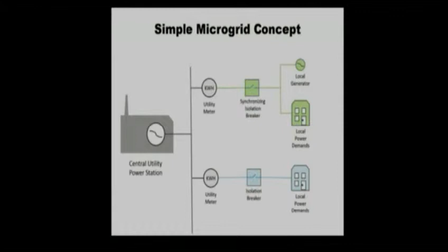So microgrids can actually strengthen the reliability of the grid and also provide the voltage and frequency services that are so paramount to electricity supply. Simple concept: you just have a local generator serving the local demands, and it's operating. Most microgrids, frankly, are going to be running in parallel with the grid, not islanding, not separate, but working in conjunction with the grid most of the time.